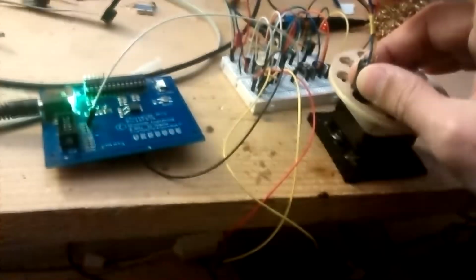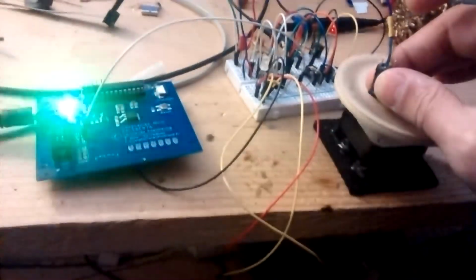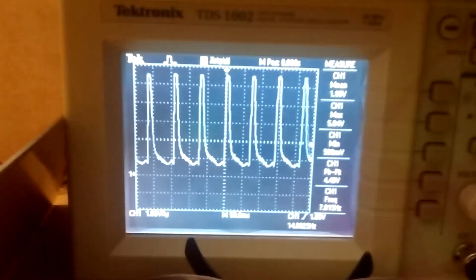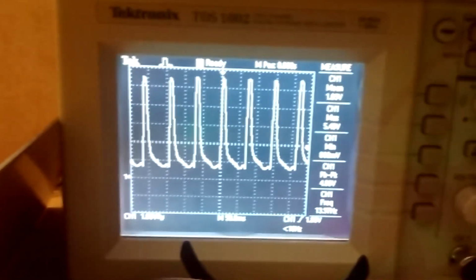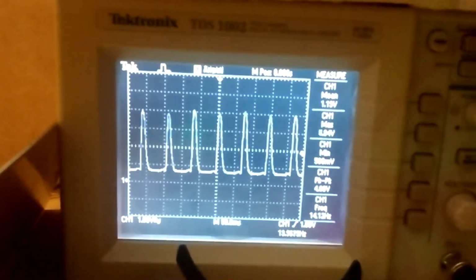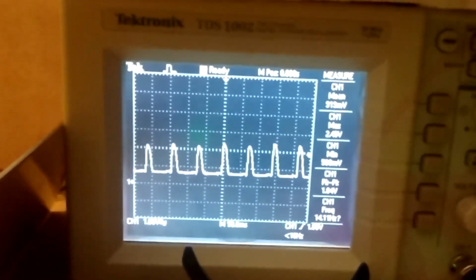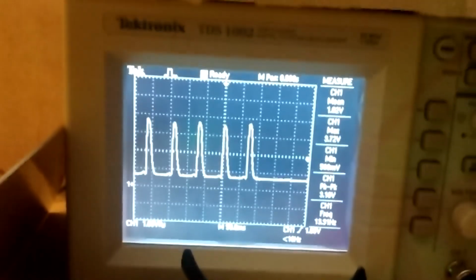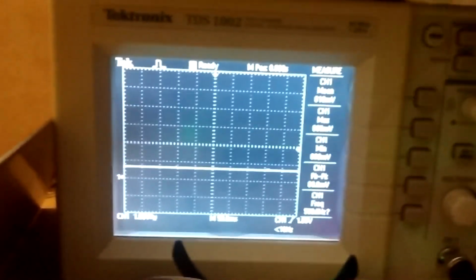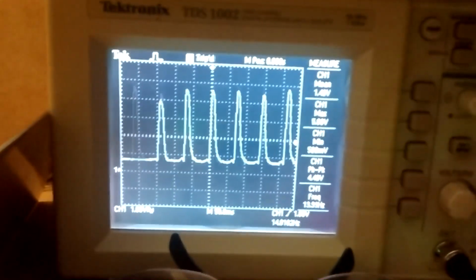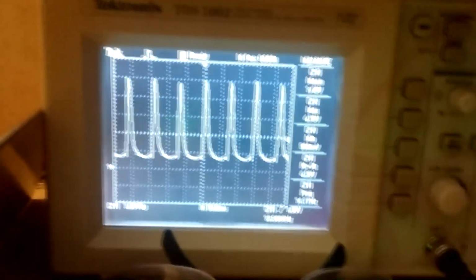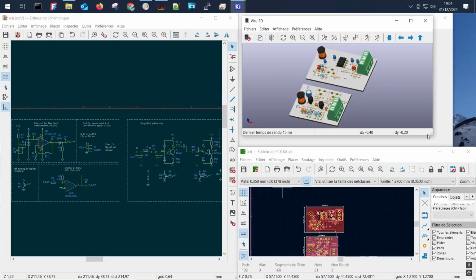According to the speed, we are going to send orders to the machine control, which is speed plus, speed minus, and main valve shut off in case of emergency and overspeed. The peripherals used in this microcontroller include the ADC and Timer 1, which is a 16-bit timer. The ADC can work at about 200 kHz, but because of the clock and the parameters we are using, we will reduce to about 100 kHz sampling, which is fine for us, as the pulses are measured to be above 1 millisecond.